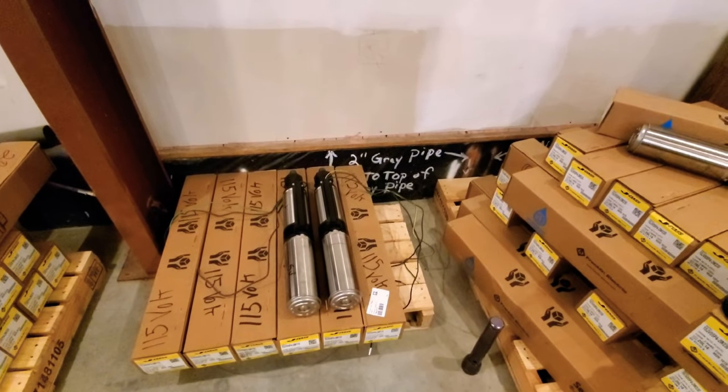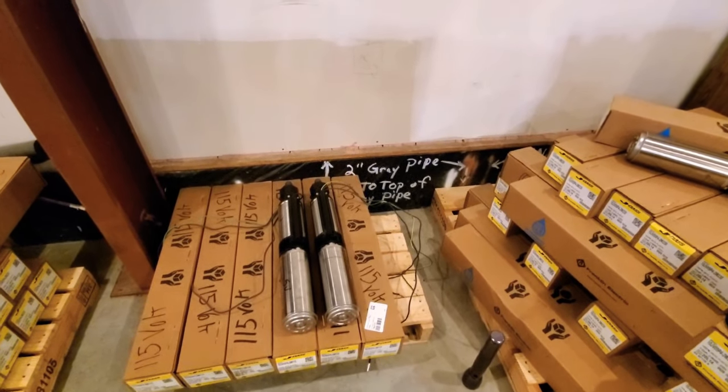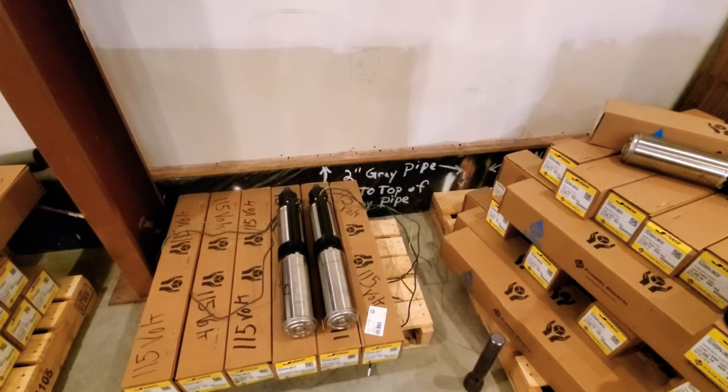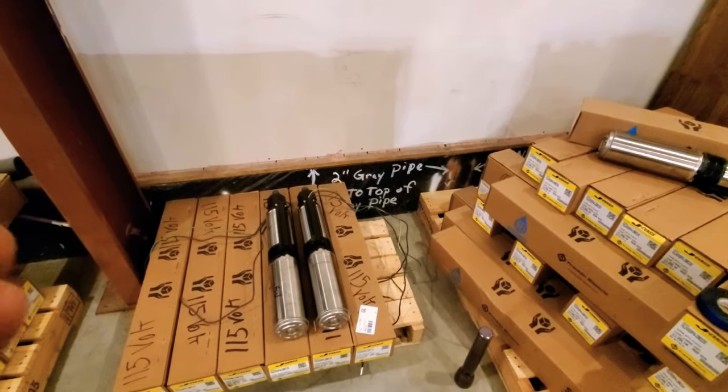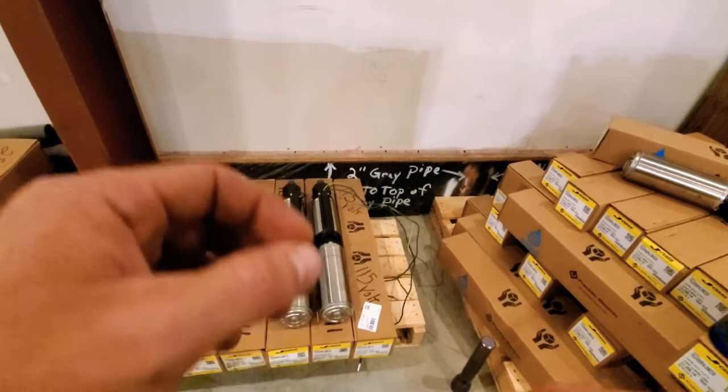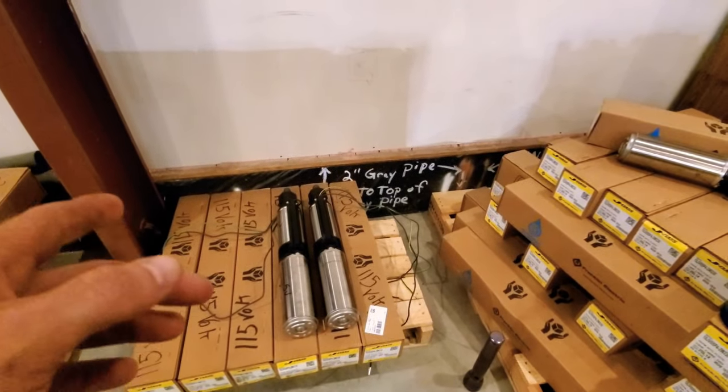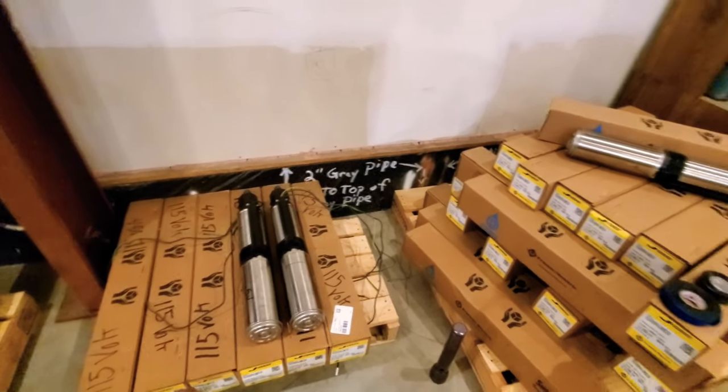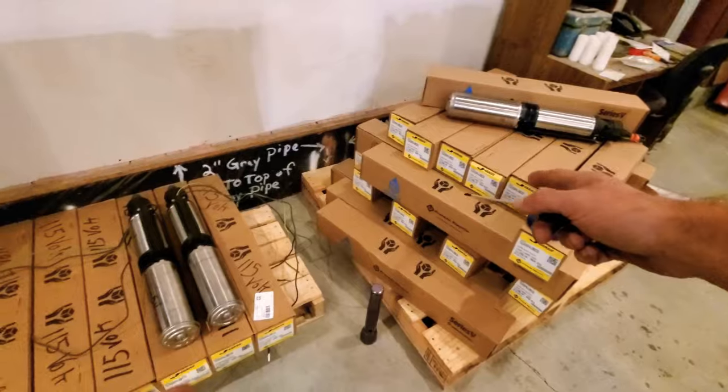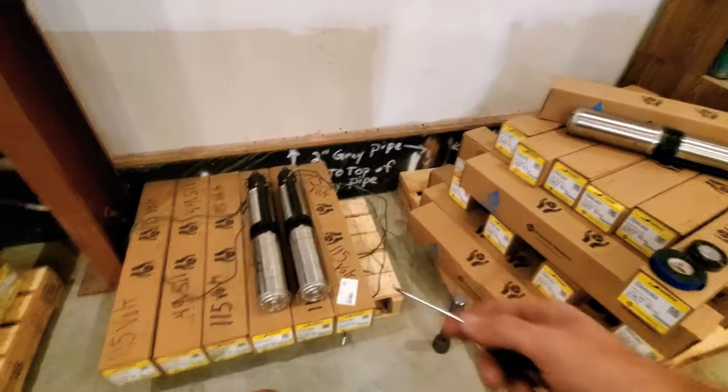The last few comments I've gotten were why is my brand new well pump tripping the breaker? The most common reason for why a well pump is tripping a breaker after you just replaced it is that you bought either a 115 volt pump when you should have bought a 230 volt pump, or vice versa.